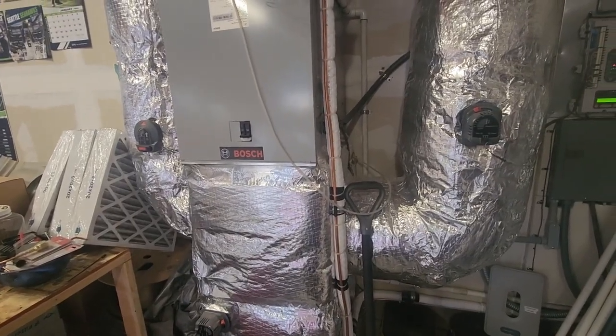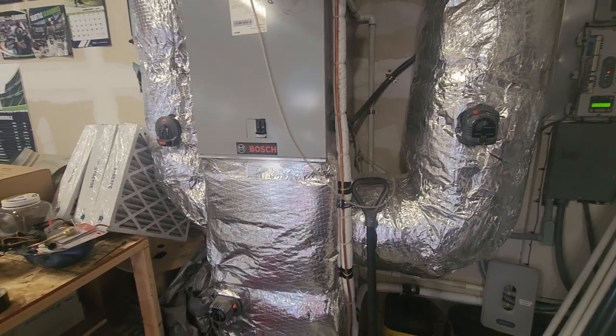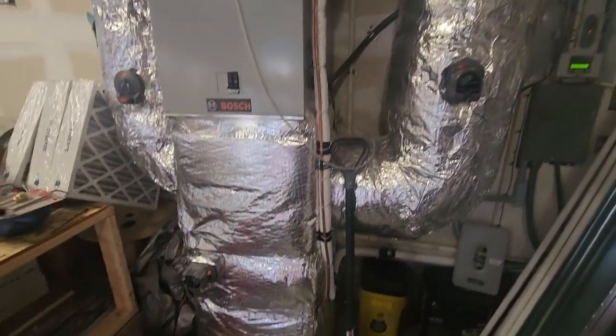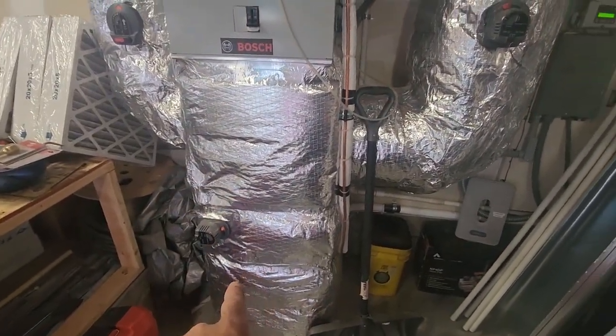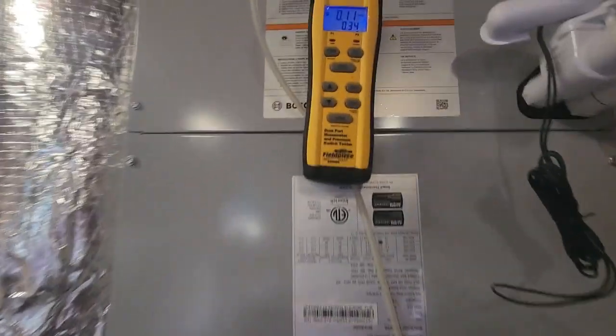Okay guys, this is the beauty of the Bosch system, the beauty of two-stage equipment altogether, coupled with that zone panel. I have the downstairs damper shut. The only one that's open is this one. And look at my static.